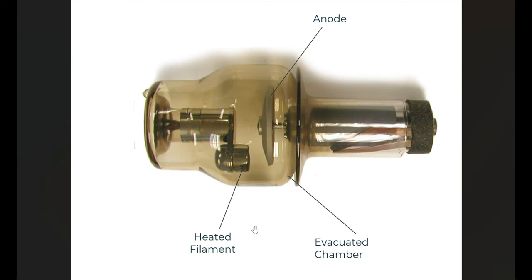The first thing I want to do is start by showing you what an x-ray tube looks like. The components that we're going to be talking about with our x-ray tube, in particular with KV and mAs, are going to be our filament, which we see here, the anode, which rotates around an axle or spindle here, and the evacuated chamber, which is where x-ray production will take place.